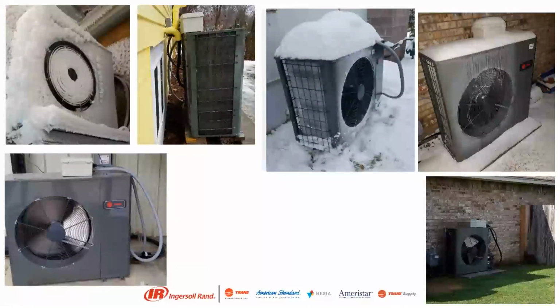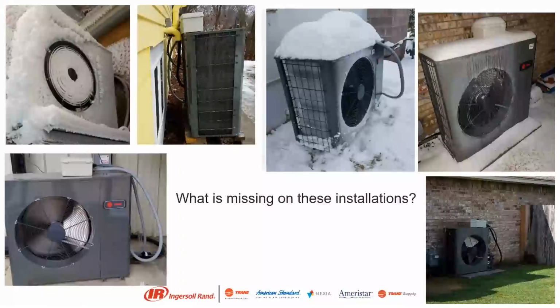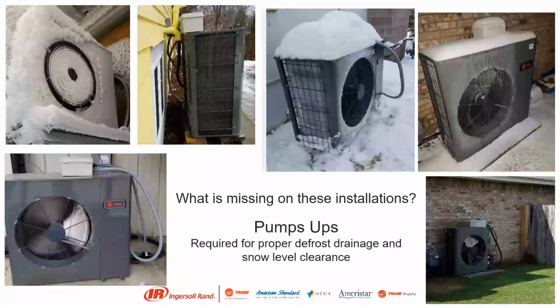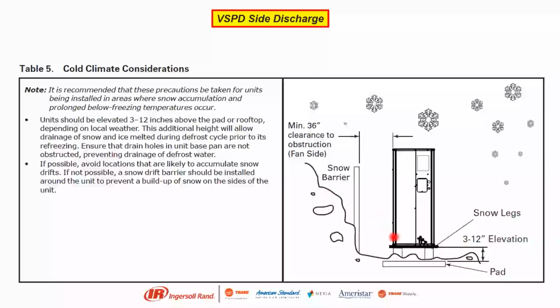I borrowed this slide deck from Mark Alkire, so he took a lot of these pictures in the field. What's missing in these installations, I just want to stress the fact that when we start icing up in our area, we need pump ups underneath. We have to get pump ups underneath, or else that defrost condensate will refreeze under there and end up lifting the unit and possibly breaking the welds. So we want a minimum 3-inch elevation underneath that, for when we're defrosting and melting that ice, so we have proper drainage down here.